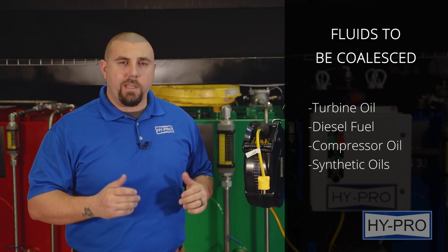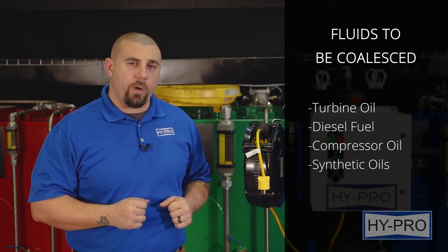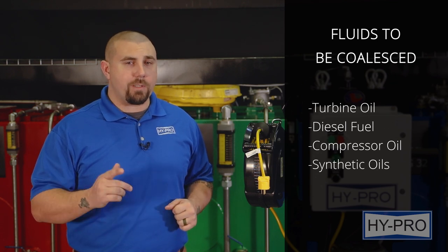Now let's talk about the types of fluids that Hy-Pro can most effectively remove free water from, or are most conducive with being coalesced. These fluids are turbine oil, diesel fuel, compressor oil, synthetic oils with an ISO VG of less than or equal to 100 and no more than a rust and oxidation additive package, and paper machine oil, just as long as it's a large enough machine and the flow rate is slow enough to account for the viscosity.